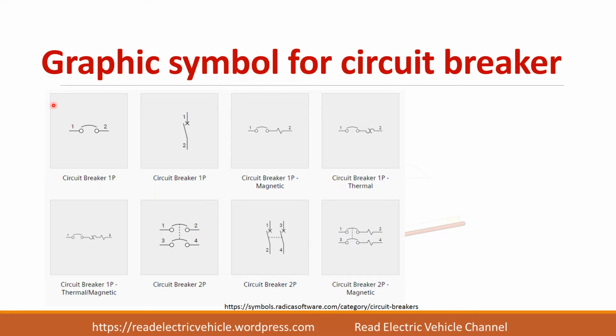First we will see what are the graphical symbols used to represent a circuit breaker. So here 1P represents the single pole breaker and 2P represents the double pole breaker. So these are some of the symbols used to represent the circuit breaker. So whatever we have seen previously is of this type they have used. And the circuit breaker, if it provides magnetic protection, thermal protection, it is represented like this. If it has both thermal and magnetic protection, it can be represented like this. So here it is for a double pole, the same thing, but two poles will be represented with the interlocking. So here also double pole, it will be like this.